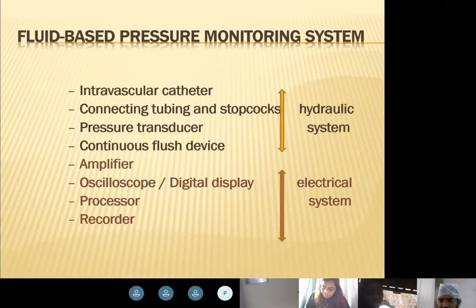So when you have a problem, there is troubleshooting. The monitor never will have a problem. It is always going to be one of these four things: a problem in the intravascular catheter, in the connecting tubing and stopcocks, in the pressure transducer, or in the continuous flush device. You should understand all these four things if you want to correctly monitor your patient or troubleshoot problems that you normally see.